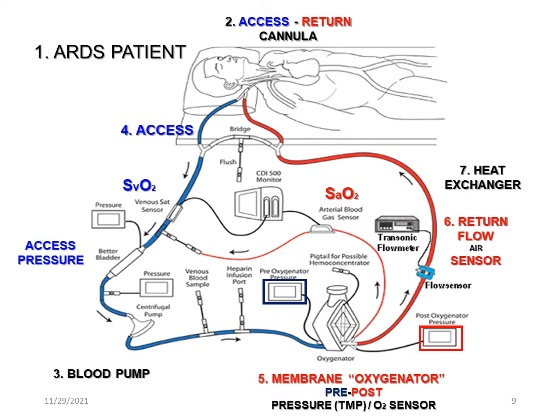There's also a heat exchanger, because before we return the blood to the patient, we want it to be at a normal temperature for the patient. We don't want to make them hypothermic, and we certainly don't want to make them hyperthermic either. So the heat exchanger will essentially just warm the blood to the required setting before it's returned to the patient. The blood is returned to the patient resaturated, eucarbic, warmed to body temperature.